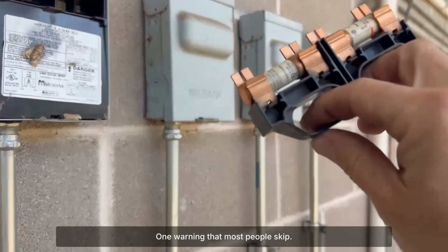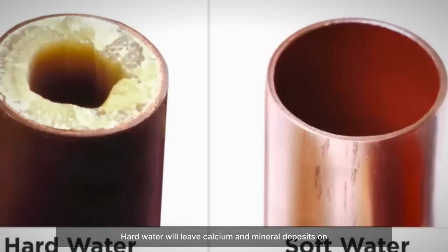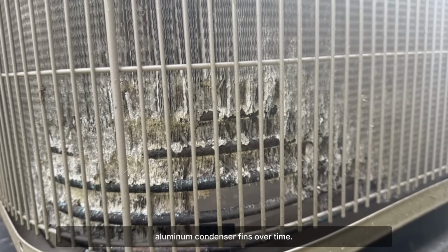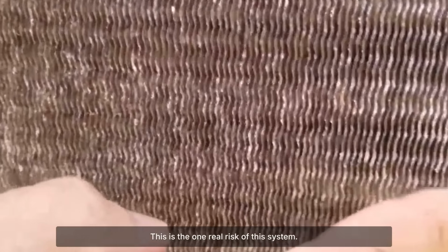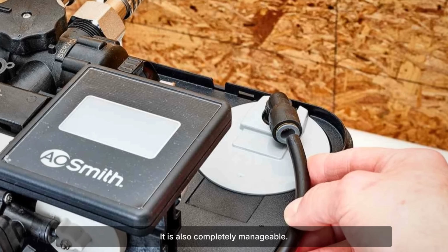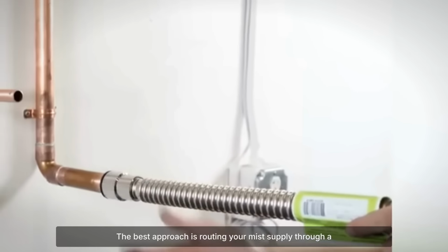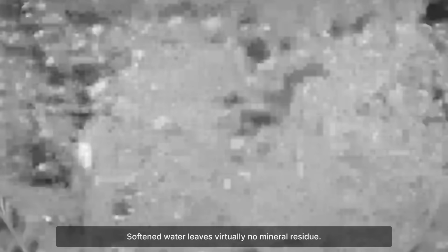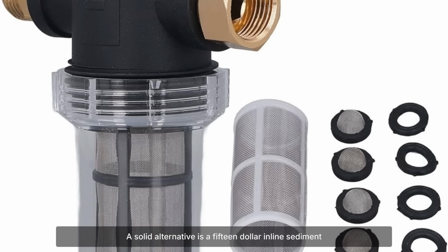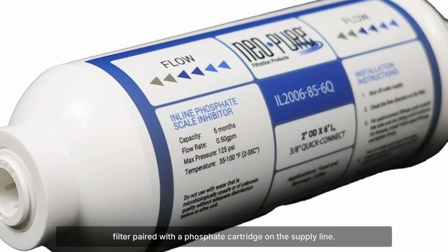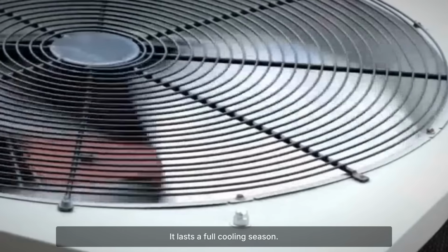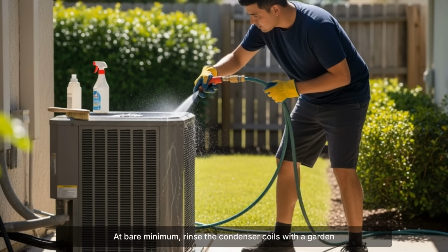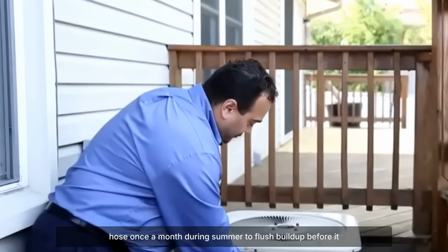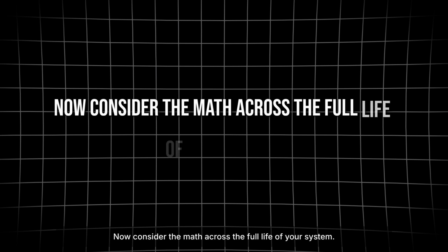One warning that most people skip: hard water will leave calcium and mineral deposits on aluminum condenser fins over time. This is the one real risk of this system. It is also completely manageable. The best approach is routing your mist supply through a water softener outlet. Softened water leaves virtually no mineral residue. A solid alternative is a $15 inline sediment filter paired with a phosphate cartridge on the supply line. It lasts a full cooling season. At bare minimum, rinse the condenser coils with a garden hose once a month during summer to flush buildup before it hardens. Now consider the math across the full life of your system.